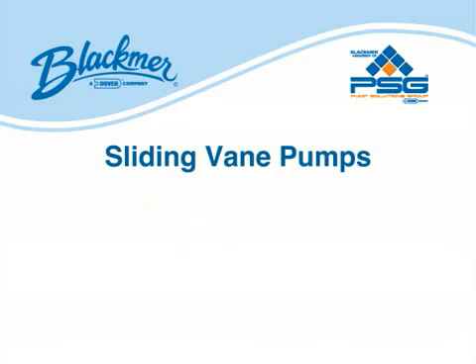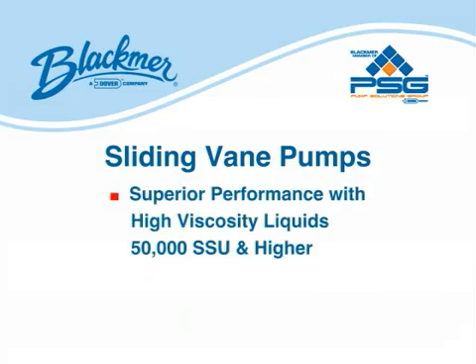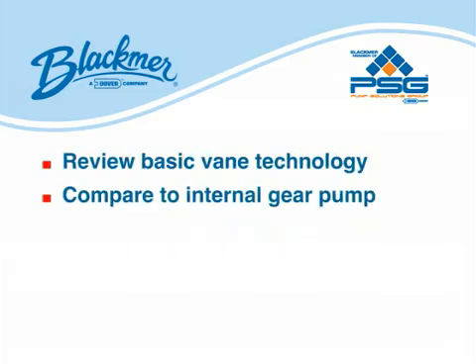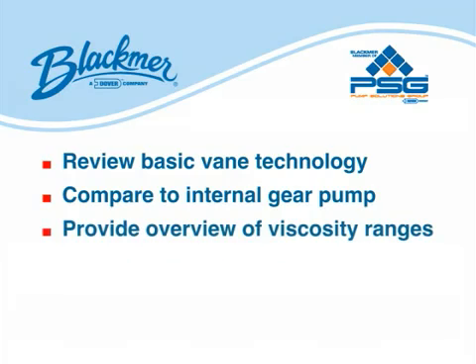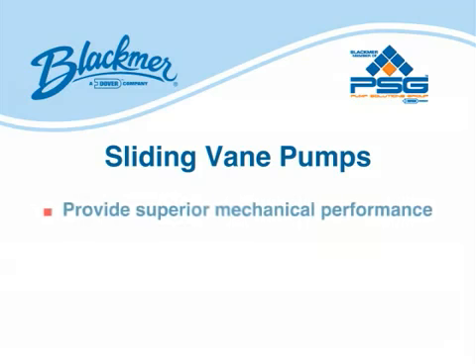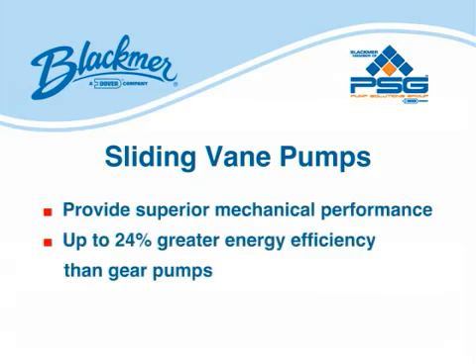But it should also be known that vane pumps are very effective at moving high viscosity liquids in the range of 50,000 SSU and higher. In this video, we will review basic vane technology principles, compare this to the principles of an internal gear pump, provide an overview of various viscosity ranges, and demonstrate vane technology effectiveness in pumping high viscosity liquids. Sliding vane pumps provide superior mechanical performance and up to 24% greater energy efficiency than gear pumps.